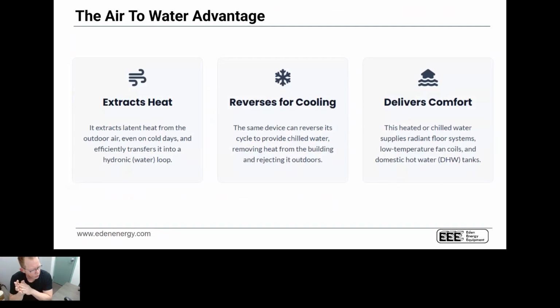As we talk about what the air-to-water advantage is, we need to understand why I want an air-to-water. Well, right off the bat, an air-to-water has very distinct advantages in that it's basically an air-to-air heat pump that is typically a lot easier to work with. It's going to be moving energy more than it is generating energy, and we'll dive into what that means exactly. But in the wintertime, we're extracting heat from the air, and in the summertime, we're rejecting heat from the building out into the air.